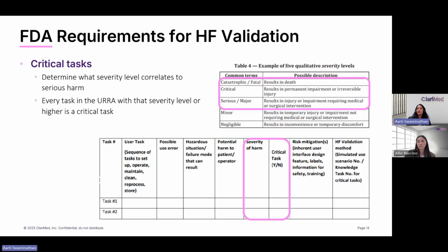For instance, if you have a blood test or nasal swabs or any other kinds of swabs, if it sort of contaminates the table area and that's inadequately cleaned later, assuming worst case scenario, somebody is actually positive for that condition and that sample is left and not cleaned off, could that later cause somebody else to be infected? What are the repercussions of that? Those are things that have to be thought of when it comes to IVDs and thinking about what really your serious harms are.